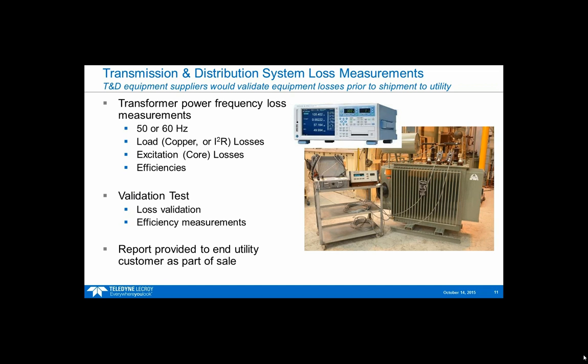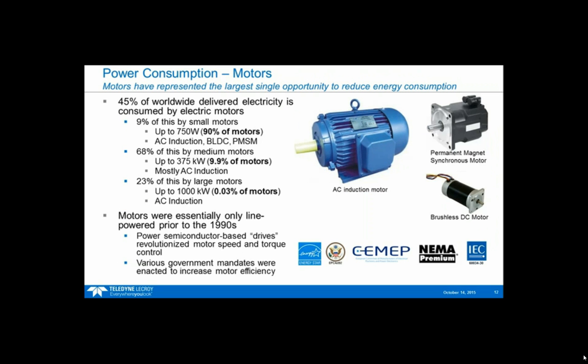Basically validating that the losses were within acceptable limits. Motors are a big consumer of power. When you look at the size motors that consume the most power, it really follows the 90-10 rule. So 90% of the motors are very small, and they consume only roughly 10% or less of the power. And 10% of the motors are very big, and they consume almost 90% of the power. But overall, half of worldwide delivered electricity is consumed by motors.